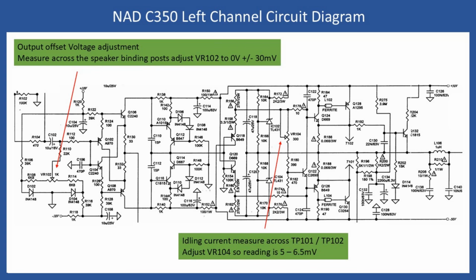In my example, starting with the left channel, you need to get a reading as close to 0 volts as possible, with a tolerance of plus or minus 30 millivolts. Once that's done, repeat the same exercise for the right channel.